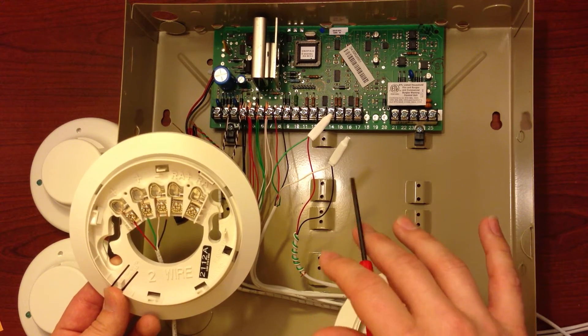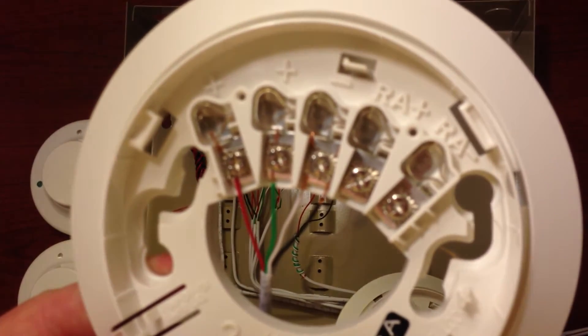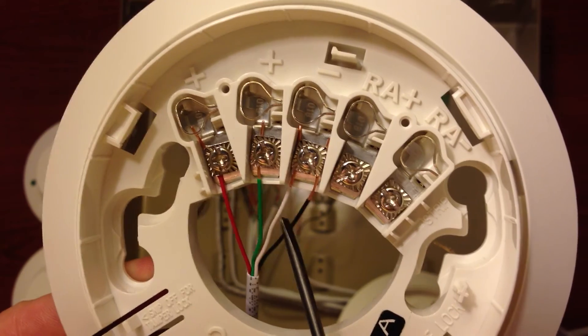Your second smoke detector, if that's the last one, will have an end-of-line resistor. But if you have multiple smoke detectors, each one of them will look exactly like the first, where you have your positive in, negative in, positive out, and negative out.